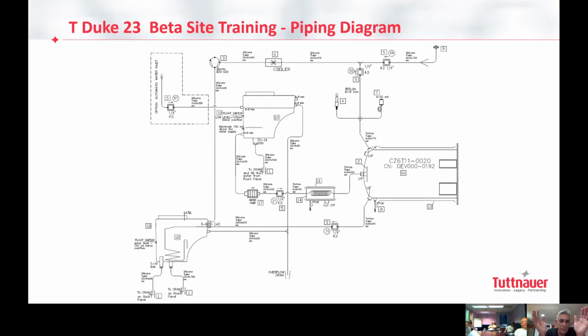It means if we are at atmospheric pressure at sea level, where the atmospheric pressure is 100 kPa, at this point we will get 8 milliamperes running between the two wires of this pressure transducer that go to the controller. Okay, an electrical circulation of two wires. It's connected with a pipe here, and it's sensing the pressure inside the chamber. The pressure transducer translates the pressure it is feeling into the current moving between these two wires and the controller. So at every single moment, the controller knows what the pressure is by the current it is seeing in this wire.